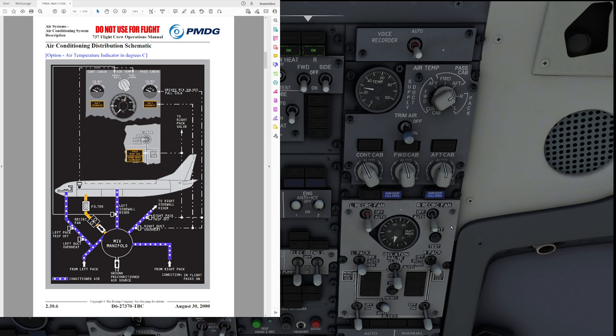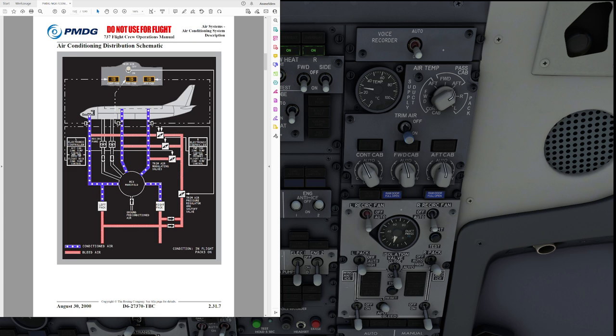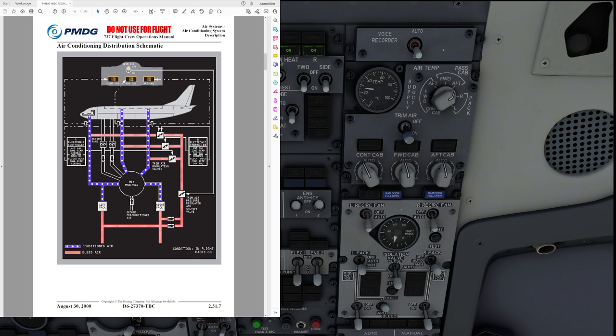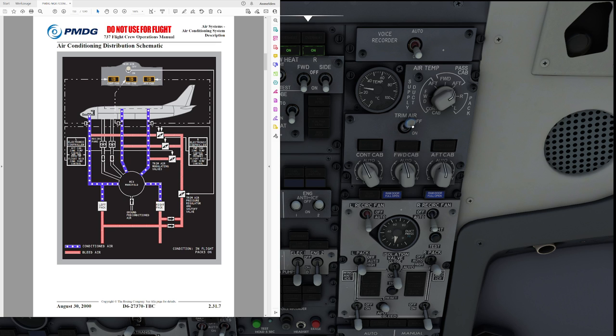In the 737-800 and 900 the system is now a little bit more complex. Prior to entering the air conditioning packs there is actually hot bleed air being taken away by the trim air system through the trim air pressure regulator and shutoff valve which is controlled by the trim air button that we have on the panel up here.